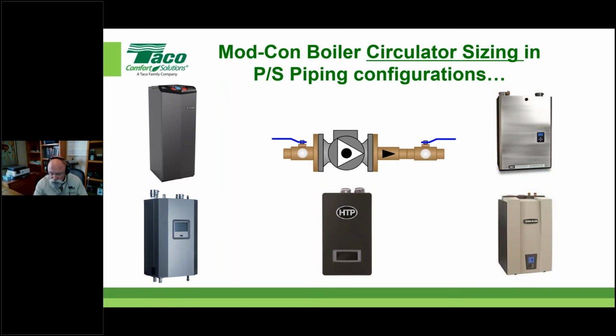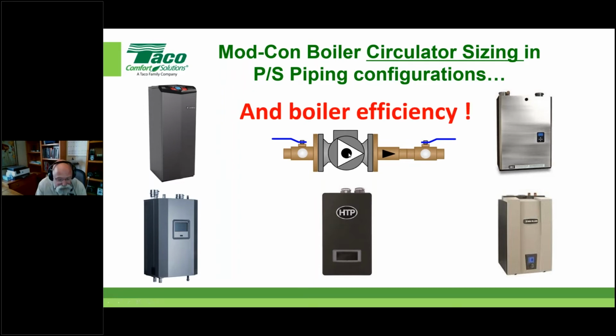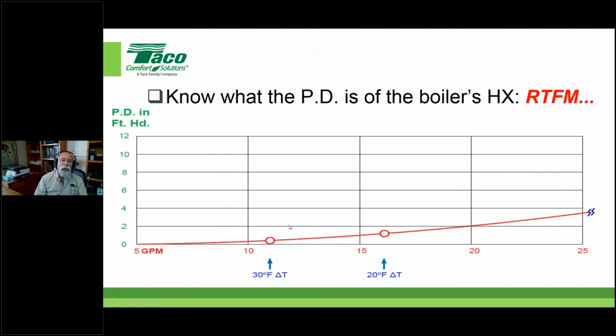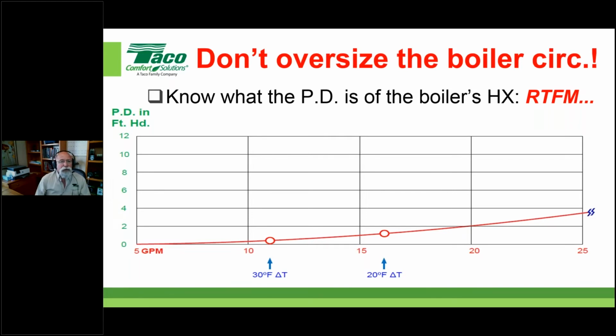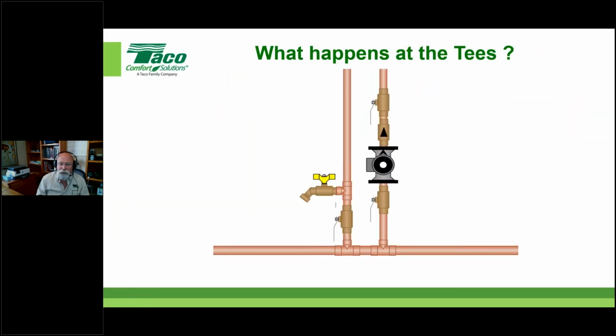So anyway, this slide is focusing on the sizing of this near boiler pump in a primary secondary configuration and how that helps us in the overall boiler efficiency. And you folks know kind of where I'm going with this one, especially how I ended it there. You have to read the manual, and the manual is what will tell you what to expect as far as pressure drop is concerned from the boiler's heat exchanger. Okay, and I can't overemphasize this. Don't oversize the boiler circulator in a primary secondary application. It's not good for anybody. Anyway, let's focus on these two T's right here, and I'm going to show you visually what happens.